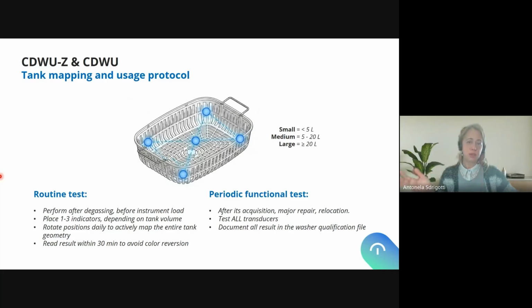I like to say, and I think this is something very easy to keep in mind, that the cavitation indicator is doing for our ultrasonic washer what a Bowie-Dick test does. We make sure that our ultrasonic washer is delivering the right cavitation energy to clean my instruments. In the same way, we use our Bowie-Dick test to make sure that our steam sterilizer is eliminating the air and that our steam is of the right quality to penetrate our items, before we even put in our load. So this is how the cavitation indicator works.